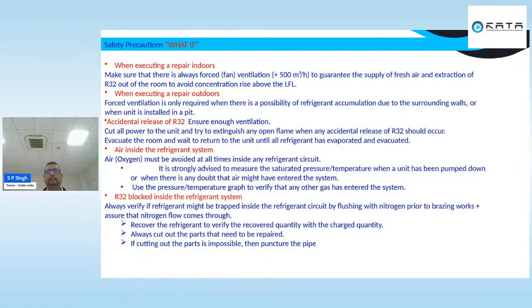If my system doesn't have proper pressure, we should understand that it is an under-pressure system, and there is a possibility that air has entered the system, and it is going to impact us. When we are doing pump down and suddenly an accident takes place, we won't be able to understand what has happened, but actually the air has gone inside, or the air was already inside.